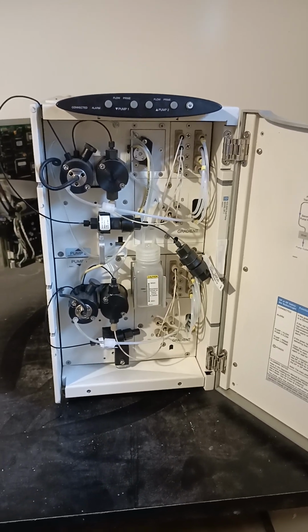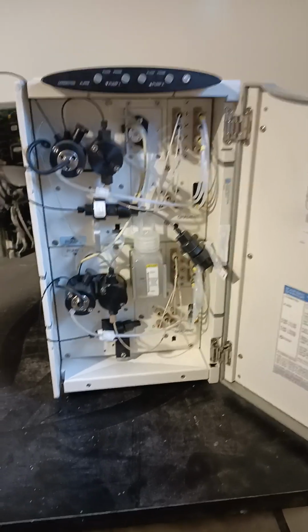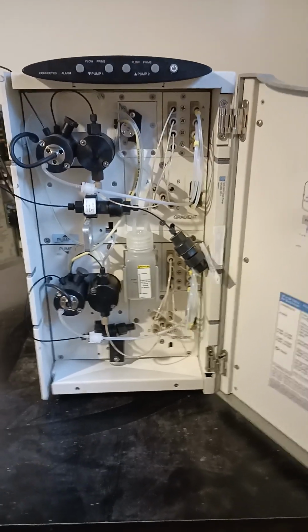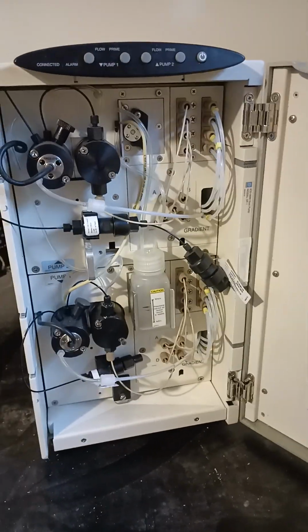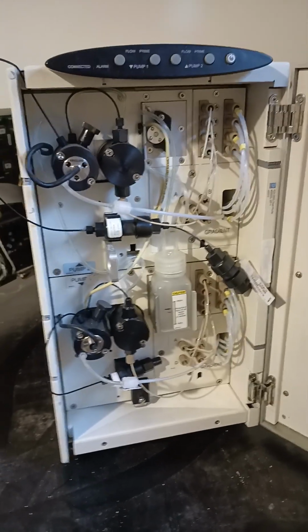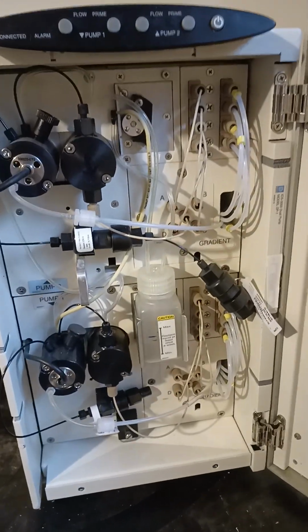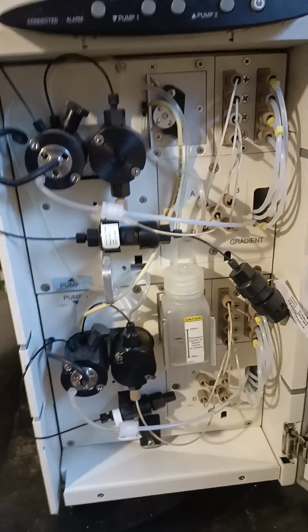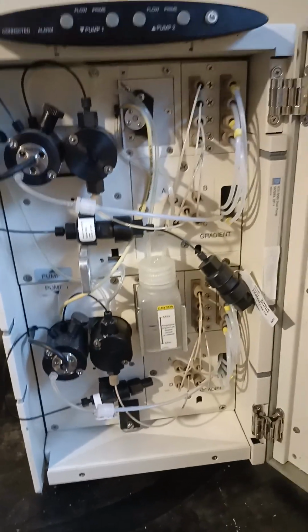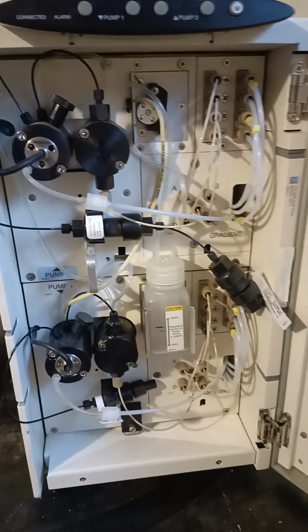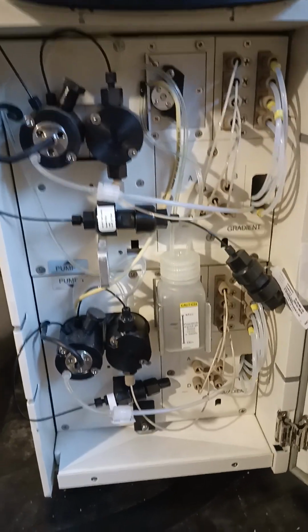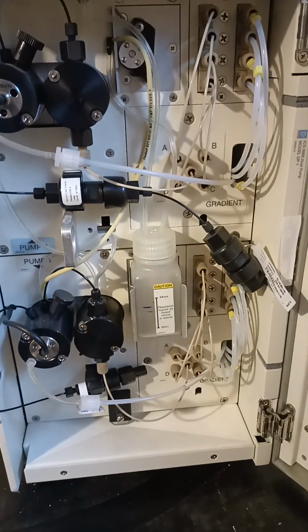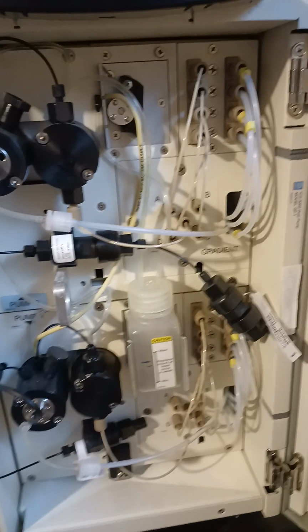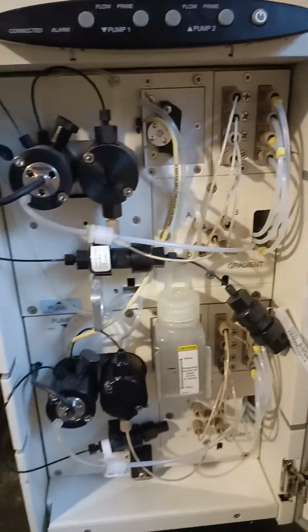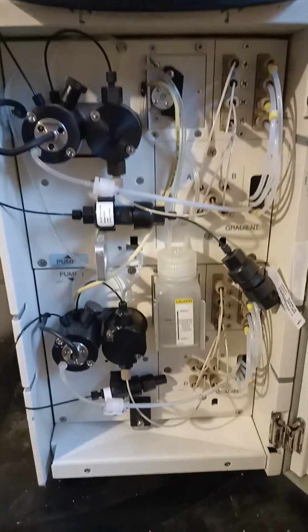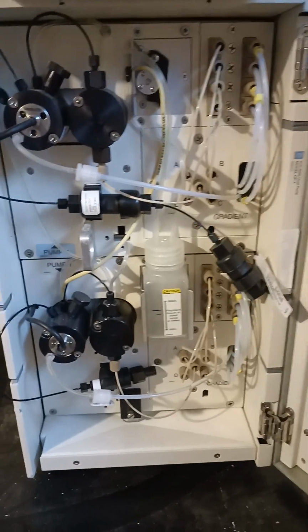This is the ICS3000 dual pump, which is very similar to the ICS5000, ICS5000 Plus, and the ICS6000. Now these are considered IC pumps, so lower pressure. They go to 5,000 psi, and the HPIC pumps are for higher pressure, and they also go to about 5,000. But the HPICs are designed to work closer to 6,000.